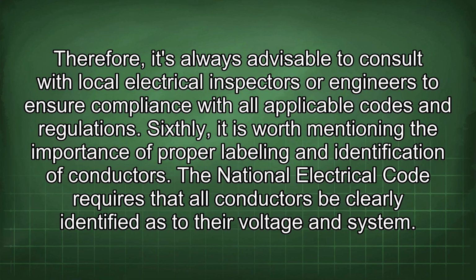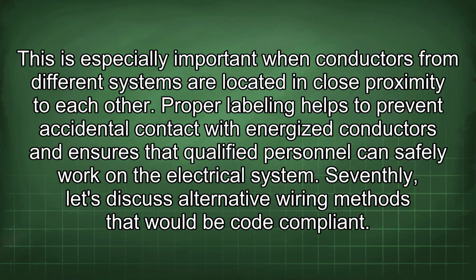Sixthly, it is worth mentioning the importance of proper labeling and identification of conductors. The National Electrical Code requires that all conductors be clearly identified as to their voltage and system. This is especially important when conductors from different systems are located in close proximity to each other. Proper labeling helps to prevent accidental contact with energized conductors and ensures that qualified personnel can safely work on the electrical system.